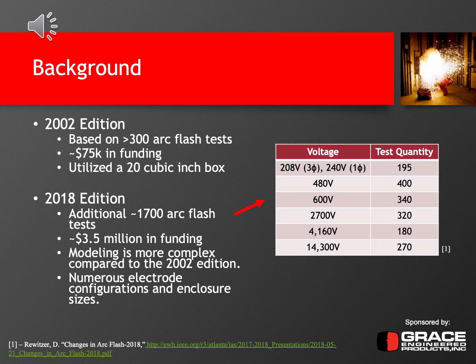So a little more background on IEEE 1584, especially on the testing and the tests that were done to determine these empirical equations used in the calculations. The 2002 edition was based on over 300 arc flash tests, and that basically came from about $75,000 in funding from various sources. And these tests utilized a 20 cubic inch box or an enclosure.